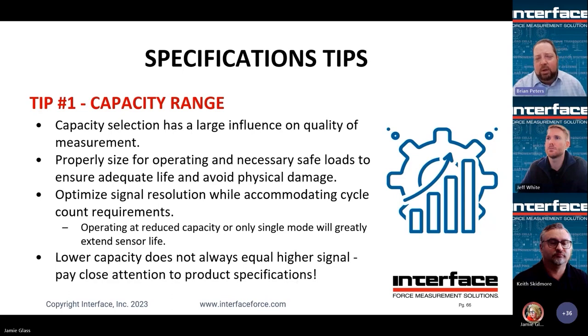Especially keep in mind too if it's single mode. So our fatigue rated load cells, as you heard from Jeff, are rated for 100 million fully reversed cycles, right? That's both directions. When you're not cycling and you're not doing cyclic loading, that also greatly reduces the chance of any fatigue risks. So if you're doing just compression only or just tension only cycles, you're likely going to be fine with a non-fatigue rated load cell, especially if you're only operating at, say, 30–50% of that load cell's capacity. So these are kind of good discussions to have with the AEs, the application engineers, to figure out exactly how much capacity you need.